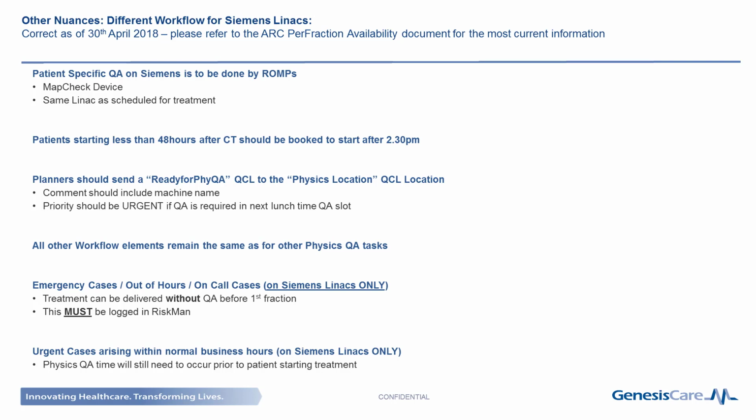Our physicist will perform a MapCHECK QA of the treatment plan on the Siemens machines during lunch breaks or after clinical working hours or at any other time the Linac may become available. For patients starting less than 48 hours after CT, the patient should be booked in to start treatment after 2:30 p.m. That way, QA can be performed by the site physicist at the very latest during the lunch break before the patient starts.